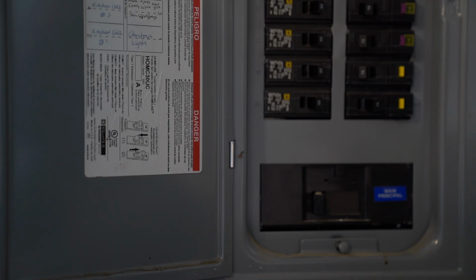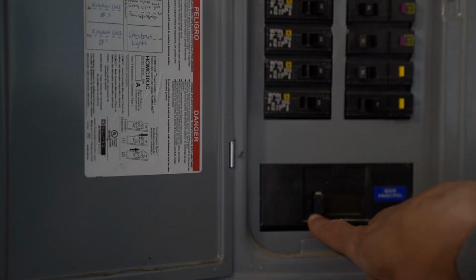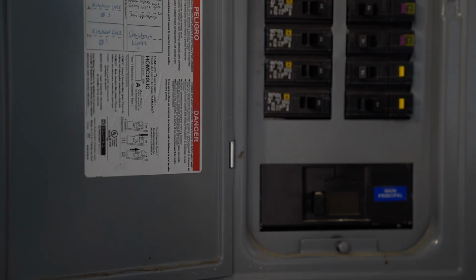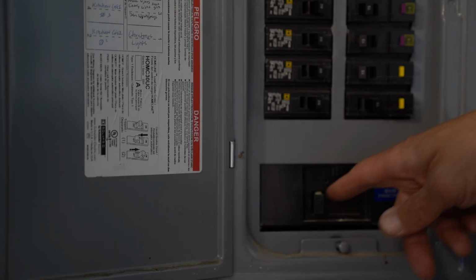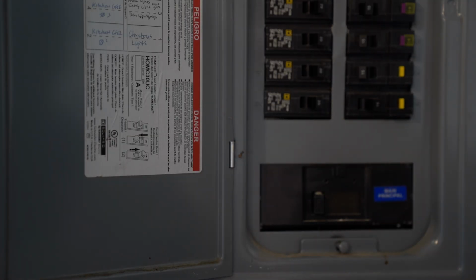All right, excellent. Another way that we can identify a main breaker is, for instance, this home is a 200 amp service, and we can see that the amperage itself is 200 amps, so that's a good inclination that we've got a main breaker there. A lot of panels can have 100 amp breakers too, so if you see a 100 amp breaker, more than likely, if it's not labeled, it'll be your main breaker, correct? Yep. Excellent. So we identify there's a problem, we go kill the power to our house, and immediately give Sunglow a call.